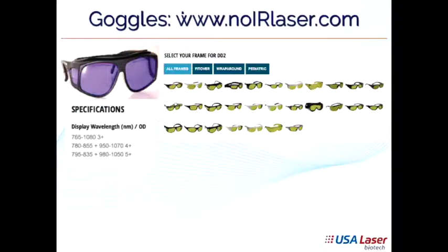The wavelength there, 765 to 1080, but the protection, the optical density, is only 3. And that's a little low. 4 should be minimum. Notice the next one says 780 to 855, and there's a gap, 950 to 1070. So already a 4, optical density 4. And then 795 and so on. You can see that.